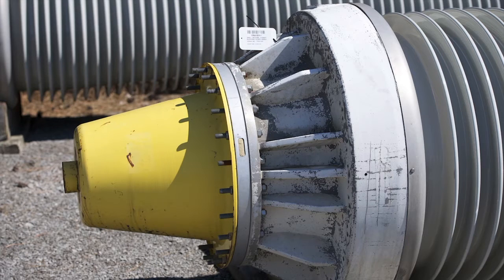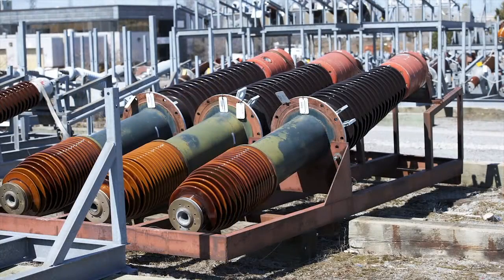The benefits of a narrower external diameter include significantly lower cost for the housing, less transformer weight, and reduction of the required clearance diameter of the embedded shielding in the lower part, that is, by up to 40%. The latter two benefits translate into lower requirements for space, weight, and oil.